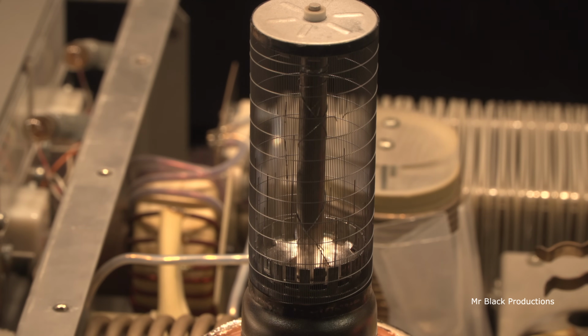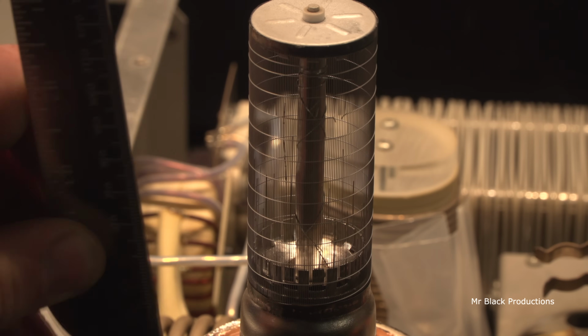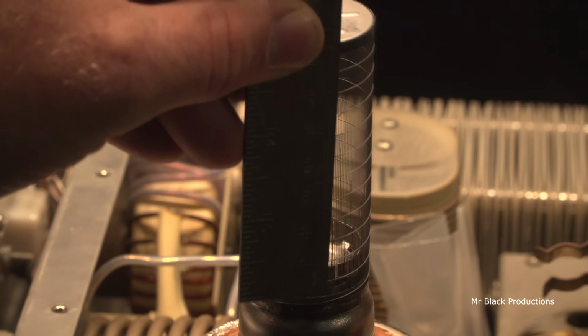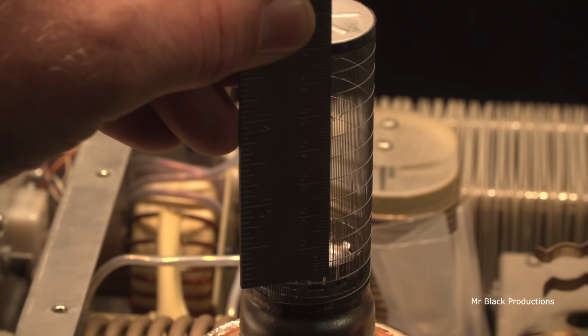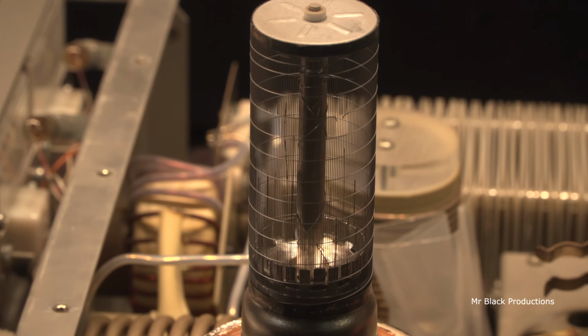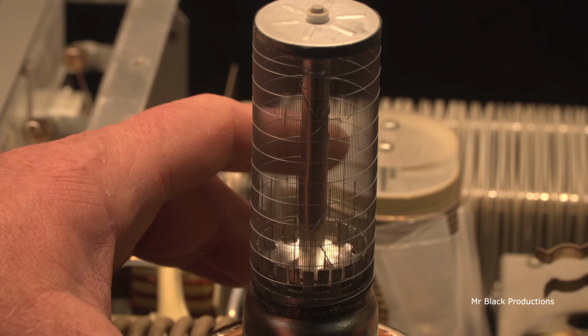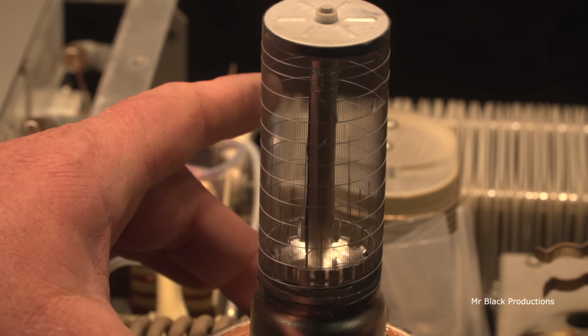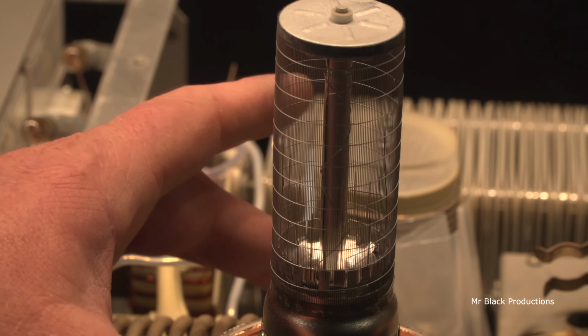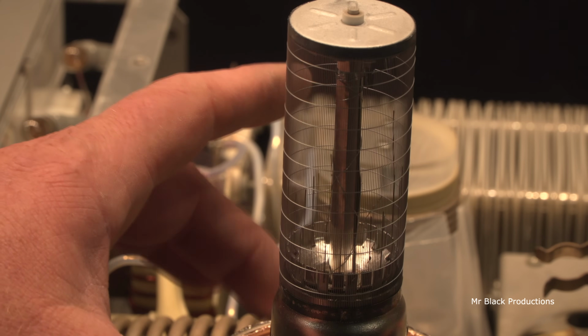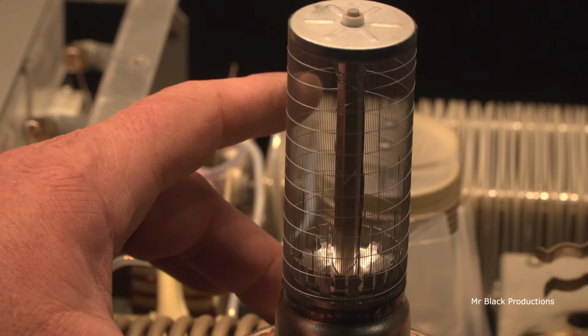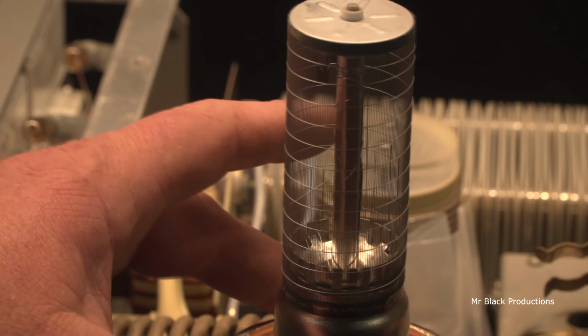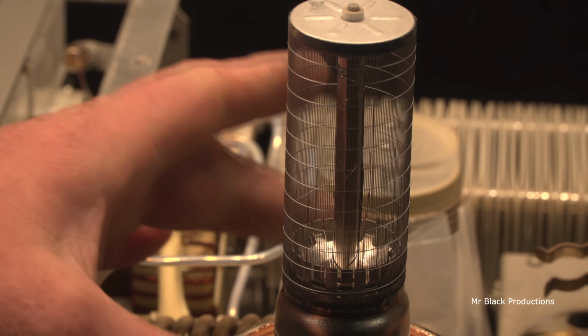If we take a ruler and we line up this finger to the opening of the screen, you'll see that the screen is shorted to the filament at some point or another. It's not only done it there, but every one of these fingers is bad because they've all broken and fallen against the screen, which is causing a high voltage short internally on the tube. Look at this. This one's melted into place.